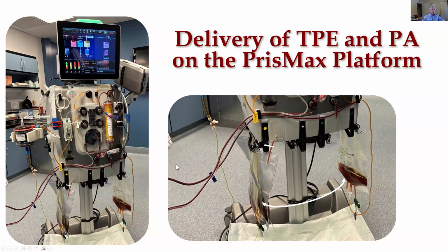And what we first devised is that we would just run the plasma out and put it in the waste bag, and when we got a certain amount of volume in the waste bag, which would be adsorptive purified plasma, we would switch that bag over to the replace bag, put the replace bag back on the collection and collect. But this is a lot of fuss, and you end up with a lot of diminishing returns because you get to the point where you really can't get this bag full enough to put over here to get a good treatment. When we tried this, it worked, but it was just cumbersome. It didn't work very well.